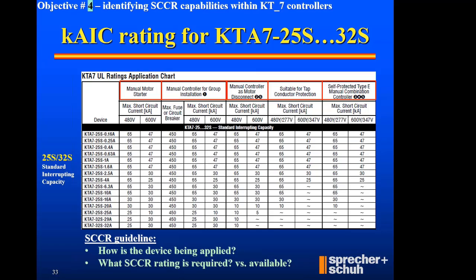So simplistically, on the left: manual starter, manual motor controller, manual motor starter, absolutely. If I look down the column, all of those KTA7 controllers have a KAIC rating, and under 480 volt, 480 delta, you notice that I can get 65 KAIC all the way down to the 10 amp model. So as a manual motor starter, sure, it's got some short circuit protection there, and that's the easiest application, because as a manual motor starter, there is no protection under those rules. It's just a motor starter.